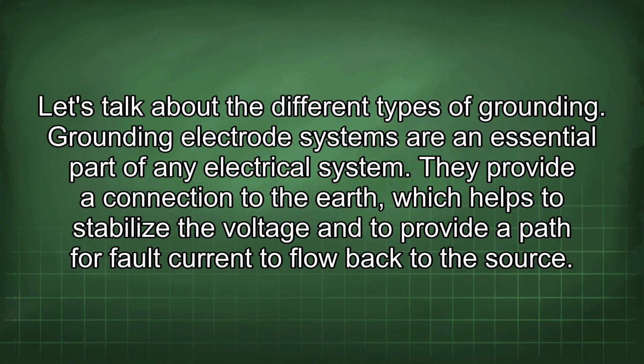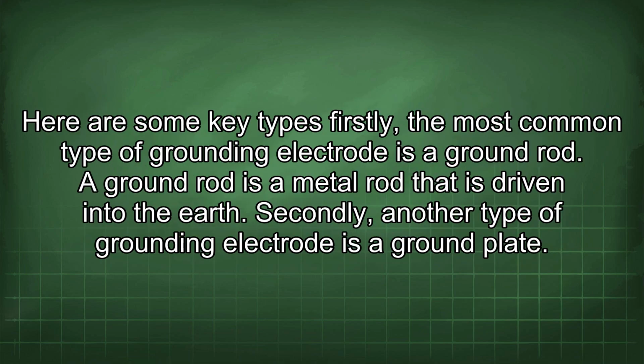Let's talk about the different types of grounding. Grounding electrode systems are an essential part of any electrical system. They provide a connection to the earth, which helps to stabilize the voltage and to provide a path for fault current to flow back to the source. Here are some key types. Firstly, the most common type of grounding electrode is a ground rod. A ground rod is a metal rod that is driven into the earth.